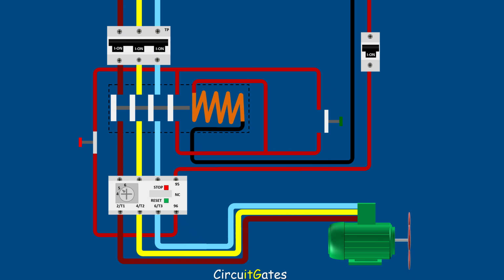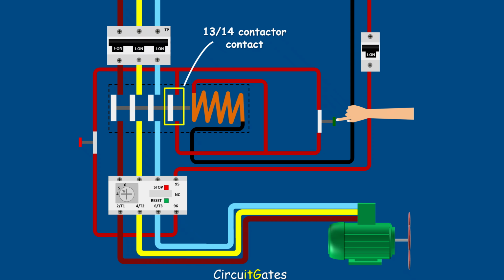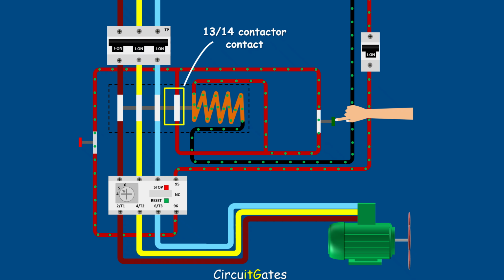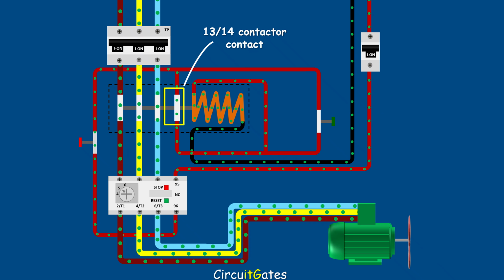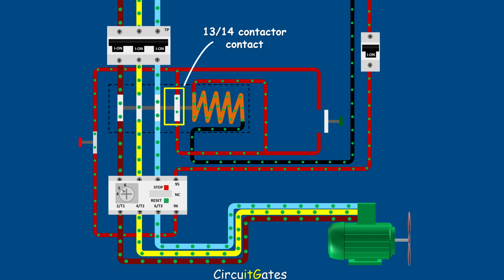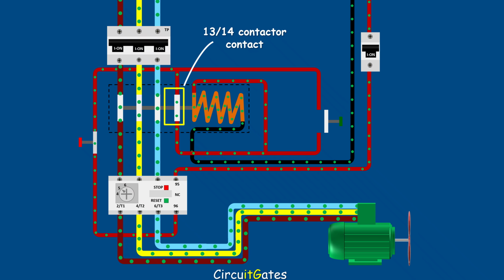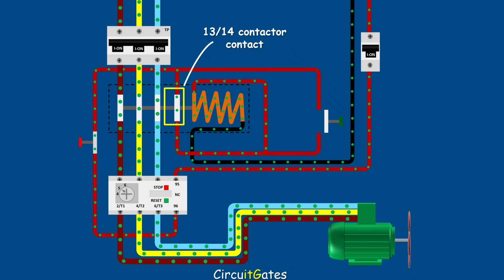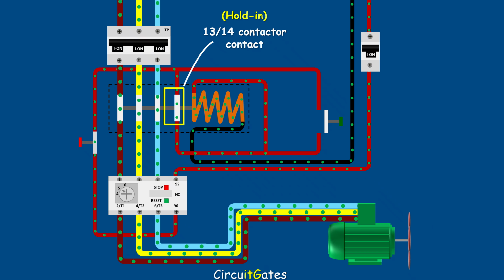The start button is connected in parallel with the 13 14 normal open contactor contact. This is because the start button is a normal open contact. Soon after being pressed, it returns to its normal open position. Current will then continue to flow to the contactor coil through the 13 14 contactor contact, so the contactor power contacts are kept in a closed position. The 13 14 contactor contact is also called a hold-in contact.